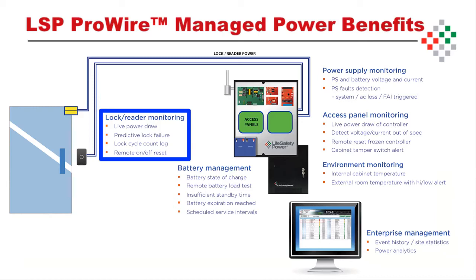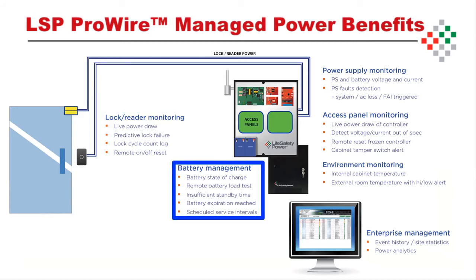Lock cycles are counted for life monitoring and remote on-off and reset is provided. Battery health may be monitored for state of charge, battery expiration time, and service interval notification. Remote battery tests may be performed on a manual or scheduled basis and battery capacity tracked for proper battery standby time.